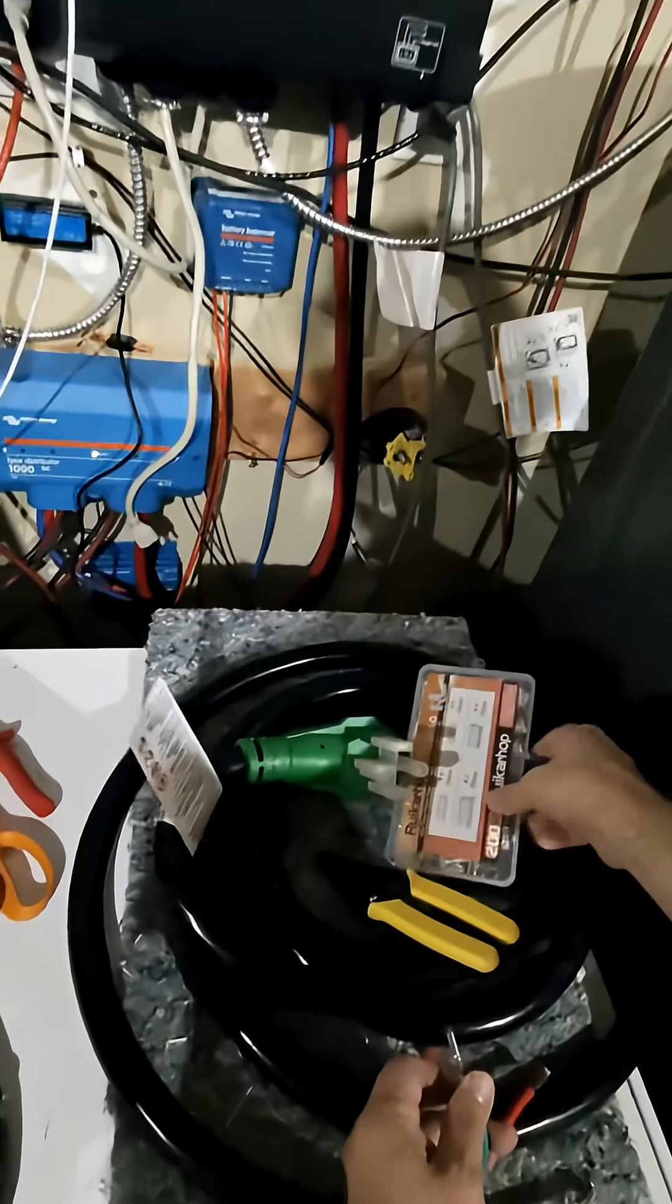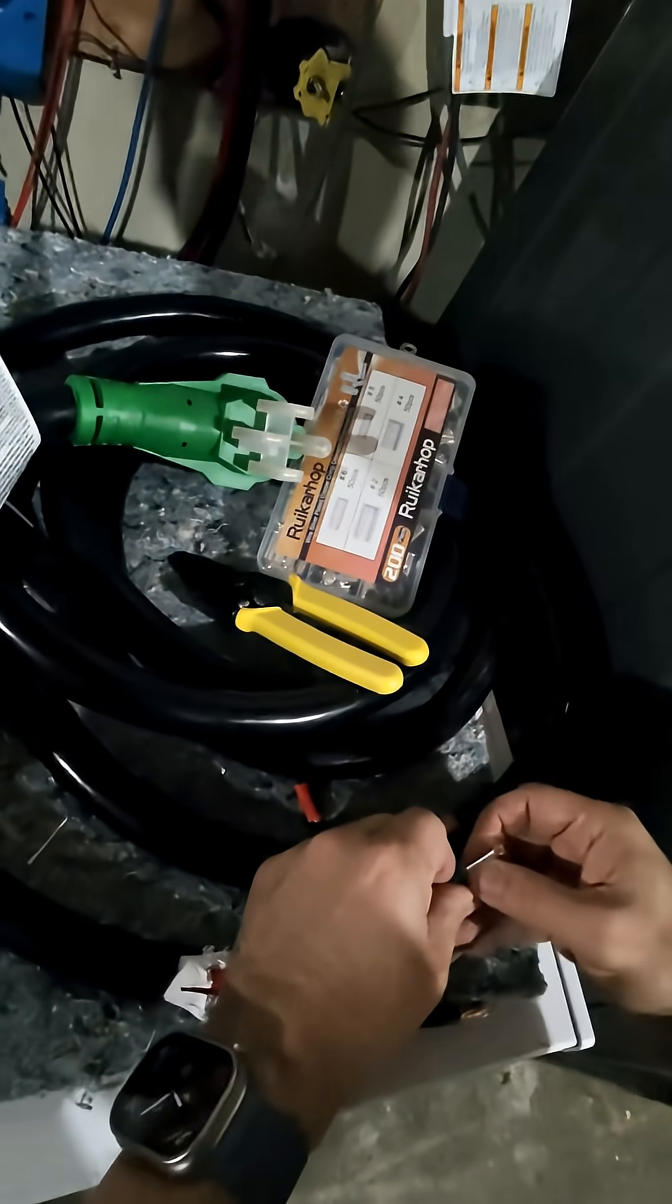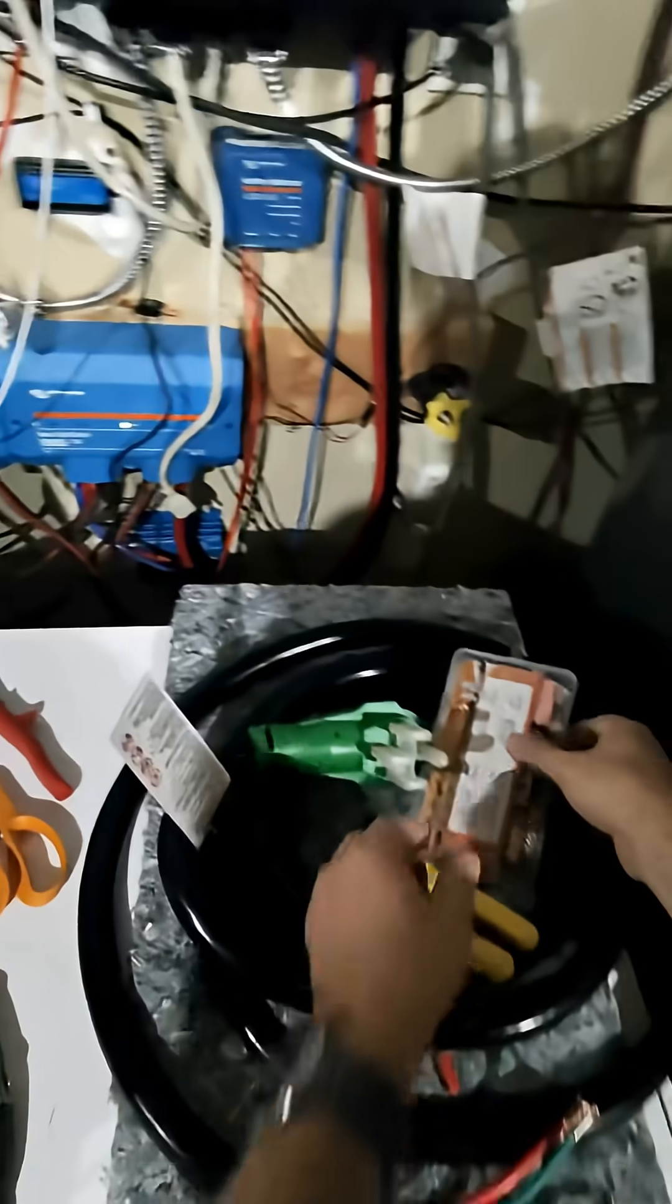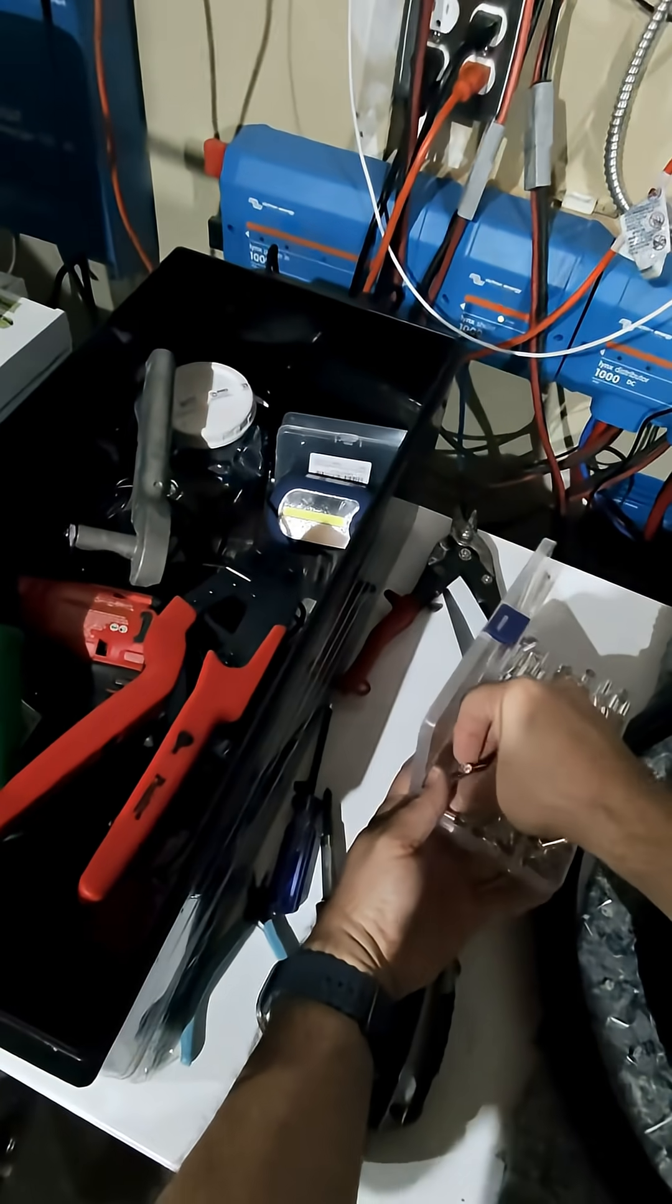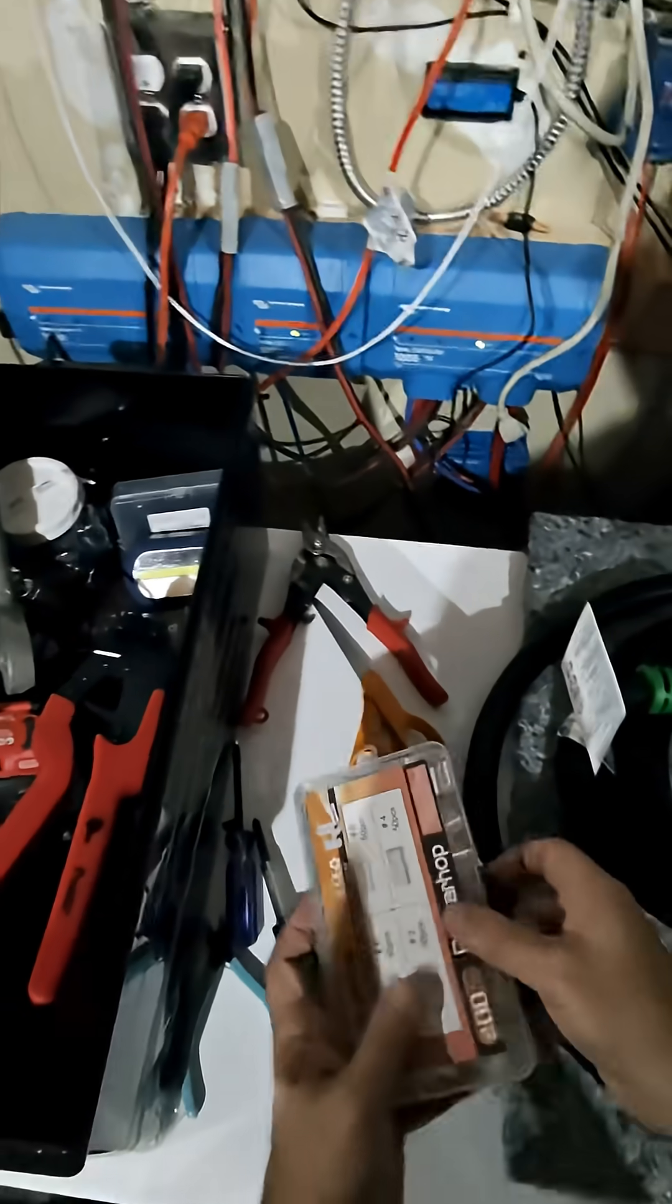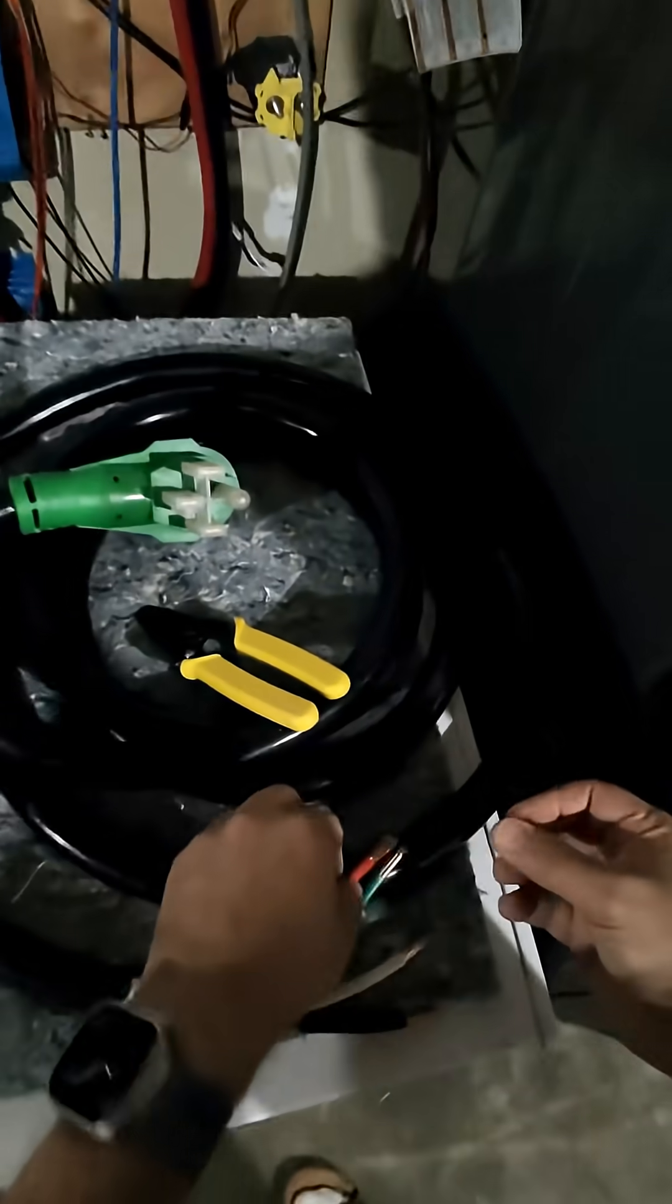I've got myself one of these ferrule kits, and the 8 gauge ferrule goes here. You can see this little excess here. I might trim that later, and let's see the number 6's. Put the number 6's on there. We'll crimp these probably with a hydraulic crimper. I do have some manual crimpers too, but you want to make sure you catch all the wires in there.